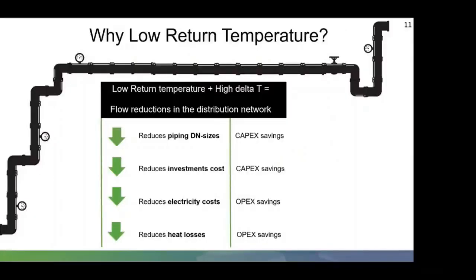So why low return temperatures? So again, yourselves, you're going to be designing the heating system for that building. So why should we try to achieve the lowest return temperature possible? Not only does this increase the efficiency, but also reduces the cost. By reducing the flow, we can reduce the pipe size, giving a reduction in the cost of the pipes, the pumps, the valves, and other components, which in turn reduces electricity cost and circulation of pumps. So if you're going for smaller pumps, again, you're saving energy in the long run.